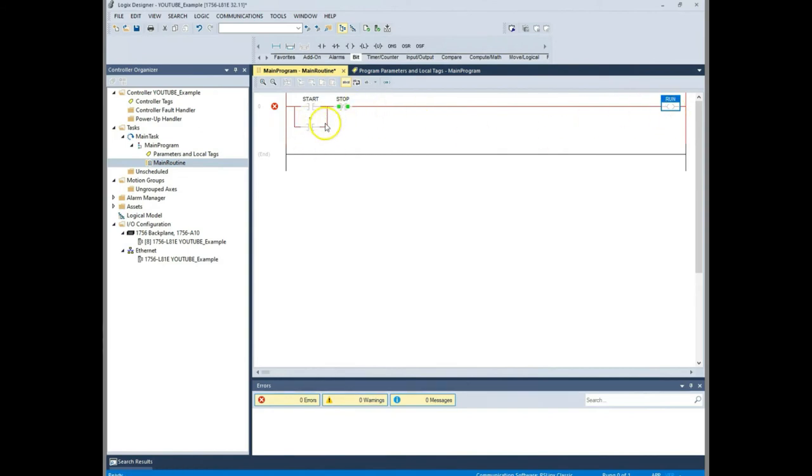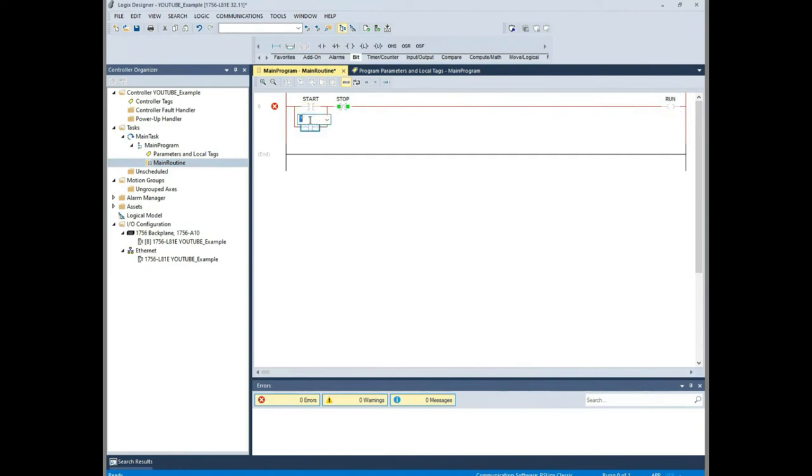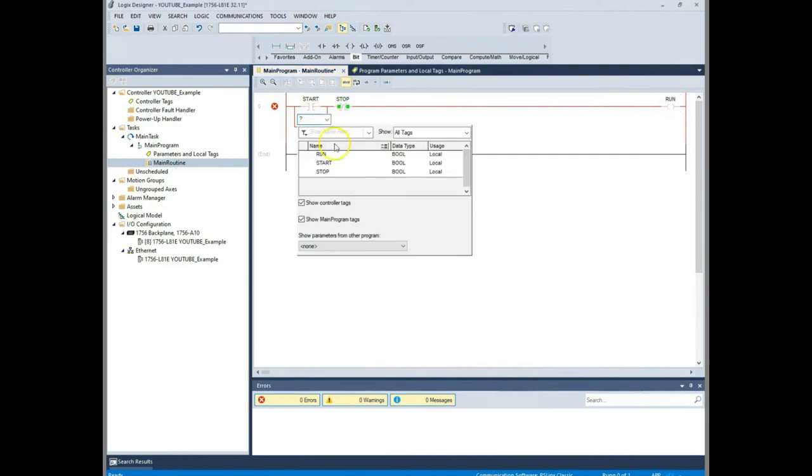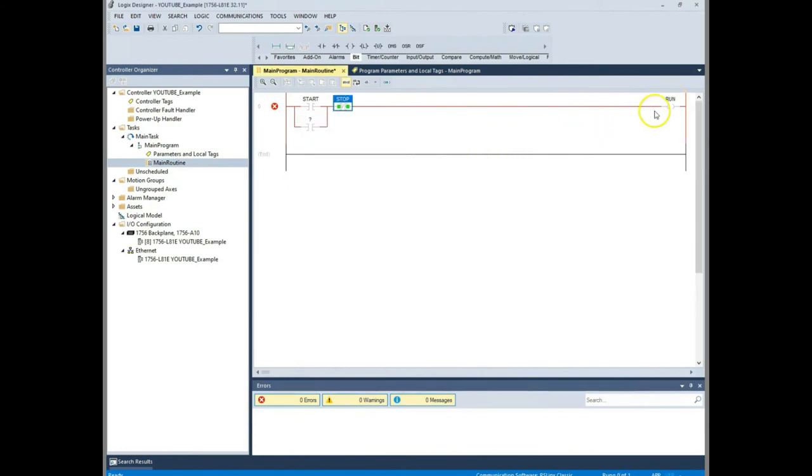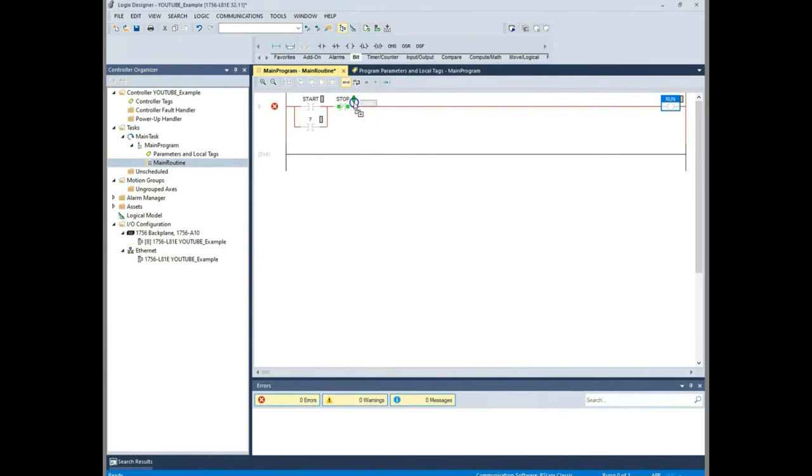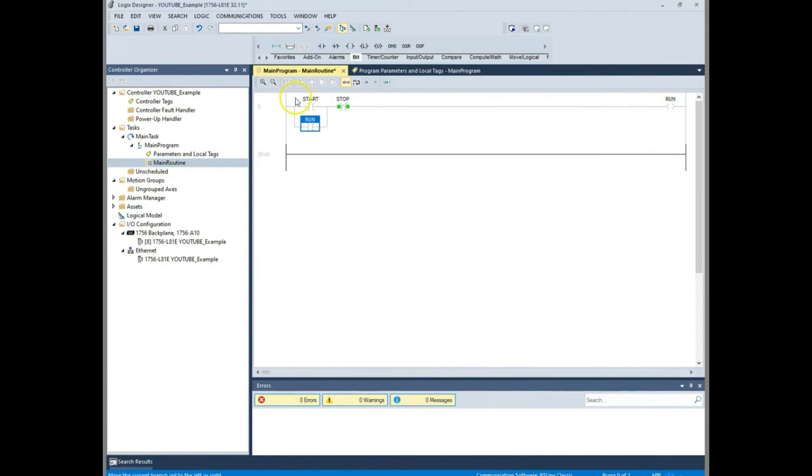Let's call that run. Now I've got two options here. I want this to come on or to become enabled whenever this run is enabled. So I can either double click my question mark and then I can choose my tag. So I want it to be my run tag here. So I can double click that run tag. Or what you can do is just simply take this tag. Now you've got to be careful about this because you don't want to click on the instruction. You want to click on the tag. See how that runs in blue, whereas the instruction's in blue. So make sure your run's in blue and you're going to hold it and you're going to pull it over to wherever you want it and let go. Now notice my red X went away. That's because I don't have any more errors now. I have tags and everything and I can download this to my PLC.